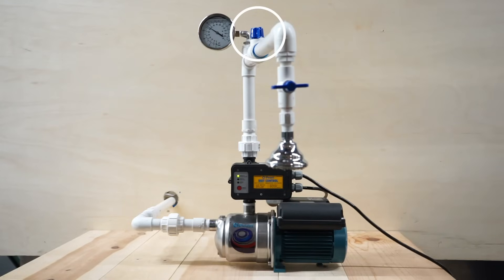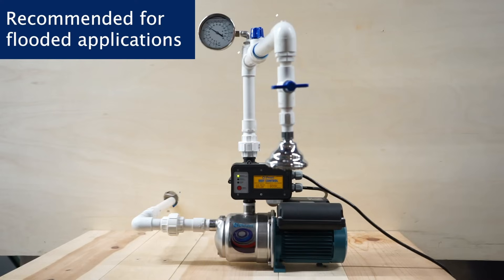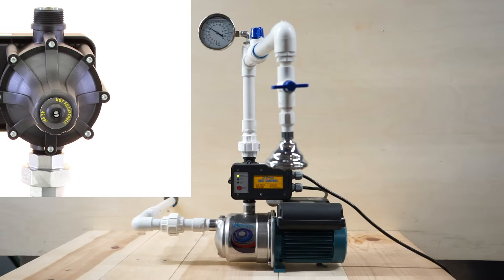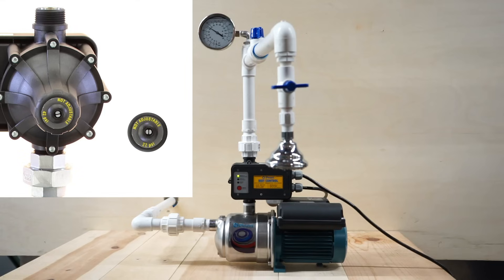Please keep in mind the following. The best control system is recommended for flooded applications, not boosting. The starting pressure of the controller is fixed at 22, 32, or 42 psi.